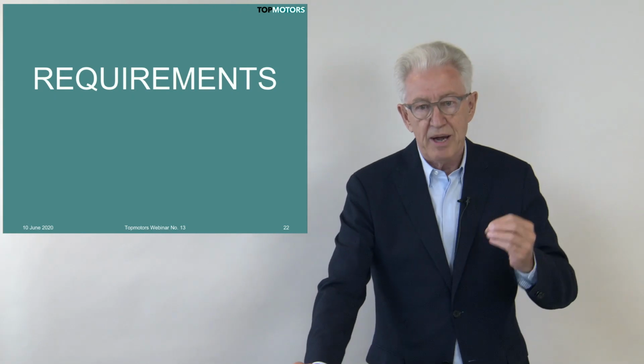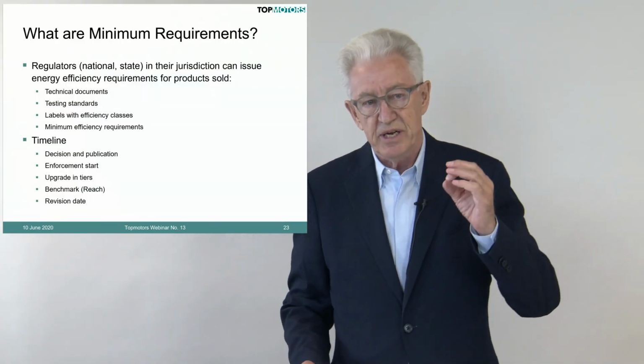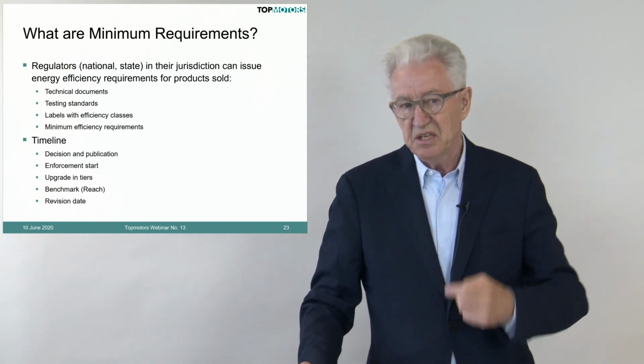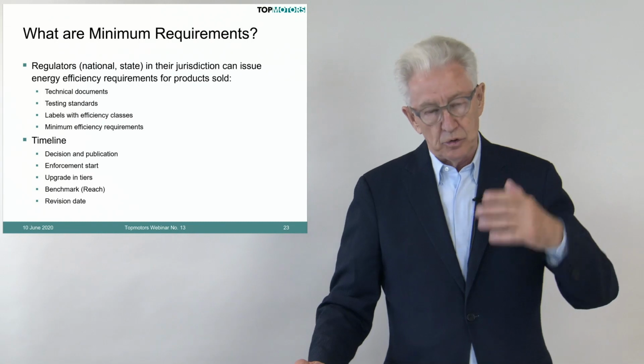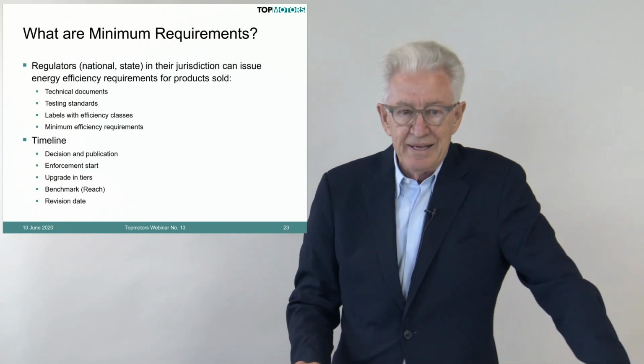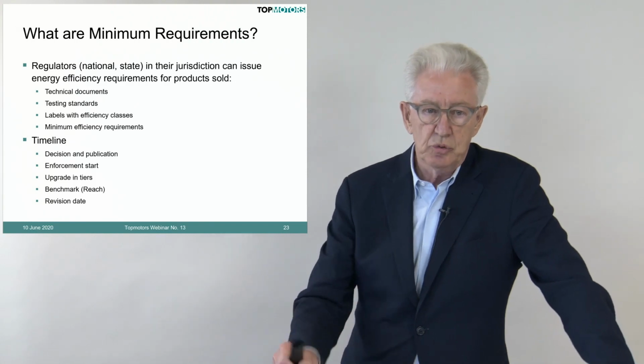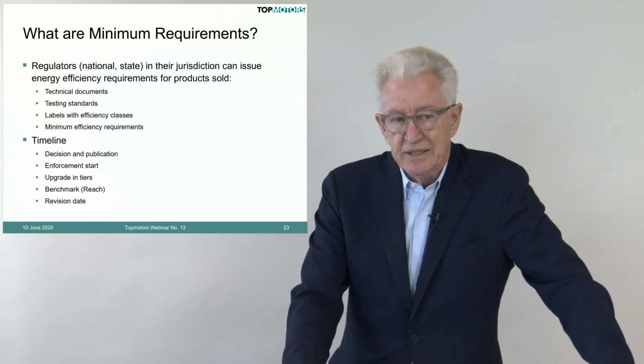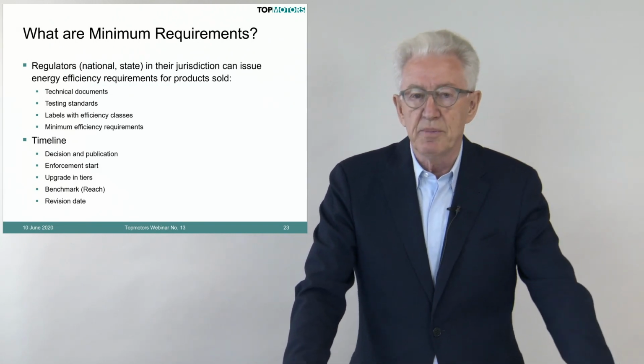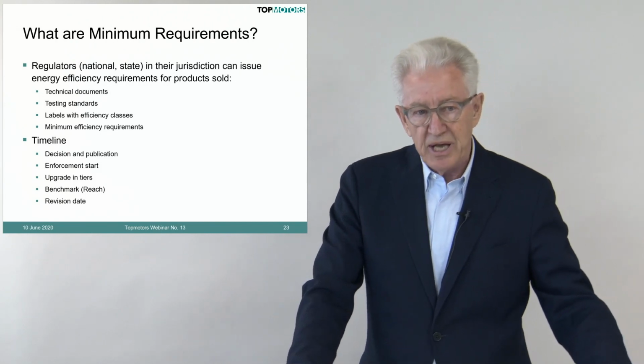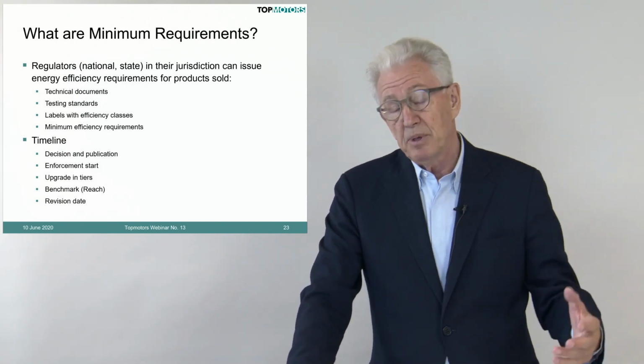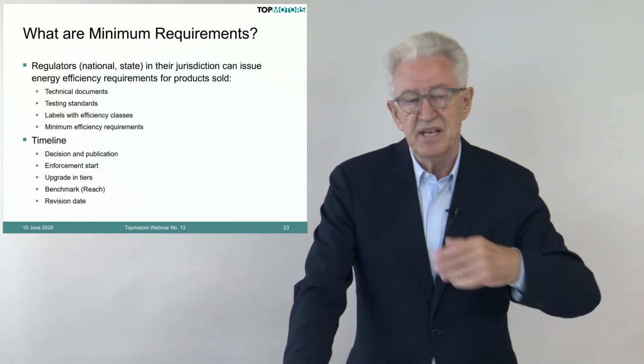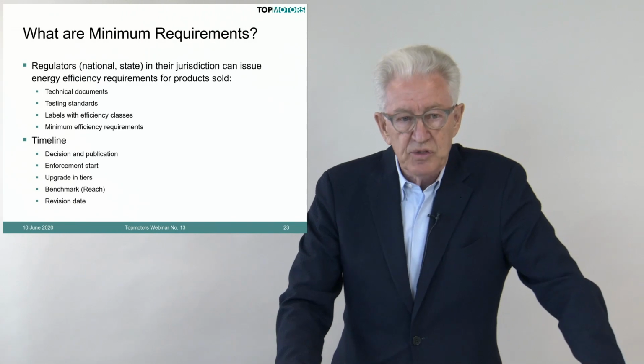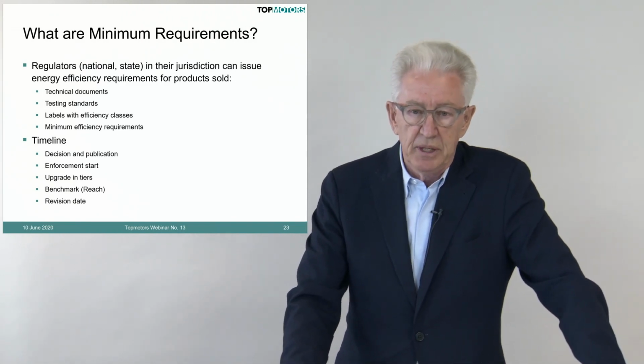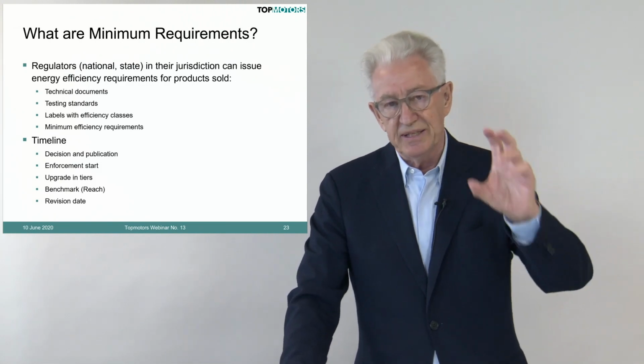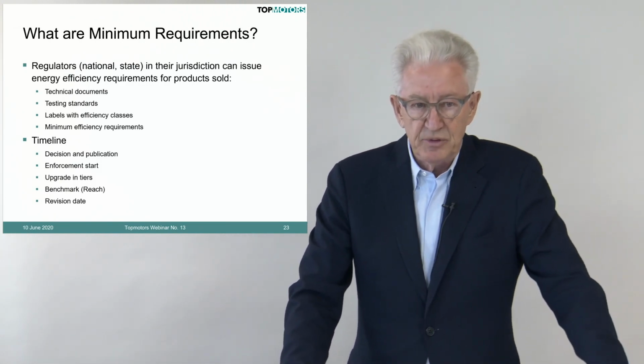Now we talk about requirements. A requirement is when a national regulator, sometimes it's a state like California, or national, meaning the USA, or a group of countries like the European Union, decides in their jurisdiction and issues energy efficiency requirements for products sold. Typically, they describe what technical documents you have to deliver when you bring a product to the market, and what kind of testing standards you have to use. If there are labels, you remember the refrigerators, they have label A, B, C, or in China 1, 2, 3. And they also define a minimum efficiency requirement: under that and that testing conditions, you have to reach 92% efficiency for that type of motor. That's what the regulators do.